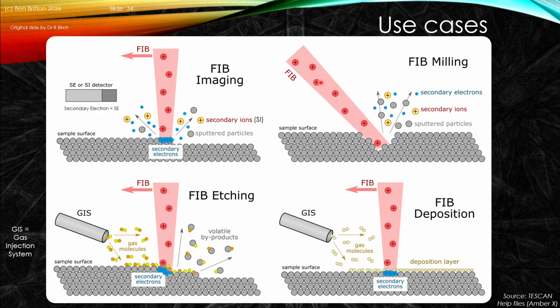If we introduce the FIB into our sample, we can sputter the material away, and so we can mill. To help us, we'll often put the sample at an angle to the beam, not always, but that's just what this cartoon is showing. We might also use the gas injection system, the GIS, and introduce a gas molecule that effectively enables us to avoid the sputtered particles sticking back to the surface.